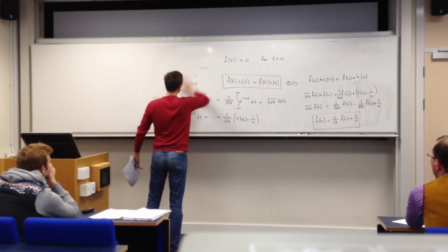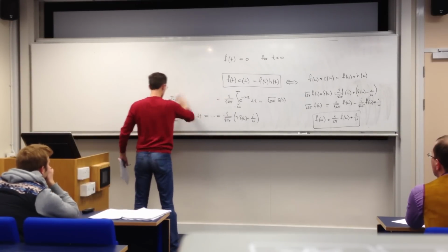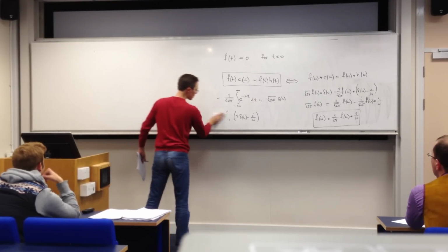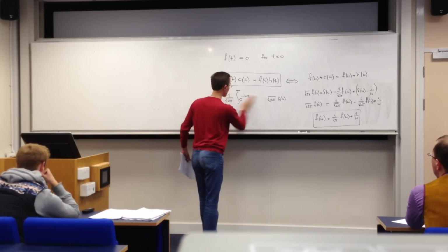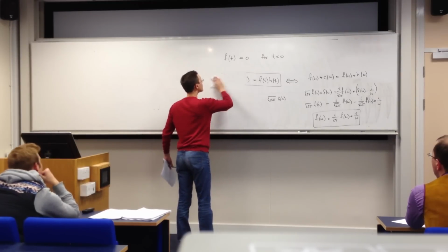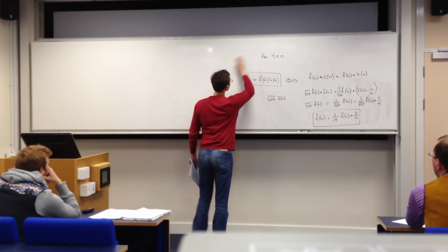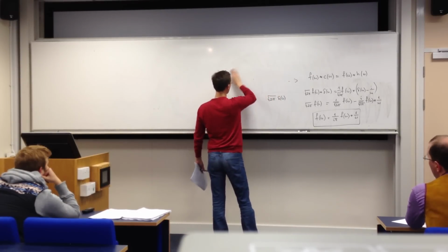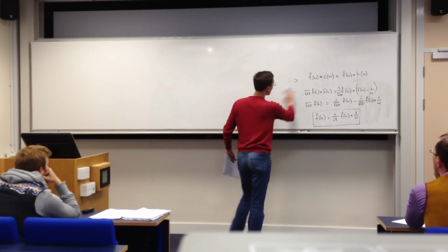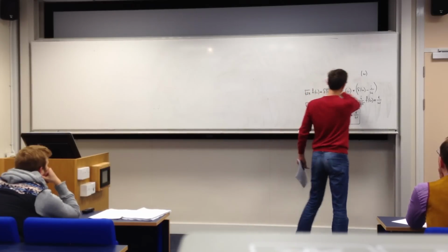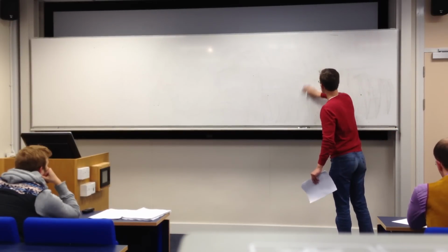And in practice, this is done, well, usually just by eye. Automated phasing procedures look at the signal integral and try maximizing the signal integral as a function of the adjustment of the phase theta. But really, for most practical purposes, it's sufficient to rotate the phase to a point where you've got the maximum intensity. And usually, if you do it by eye, the error doesn't exceed a couple of percent, because it's very easy to judge when the point has been reached, because all the signals become symmetric.